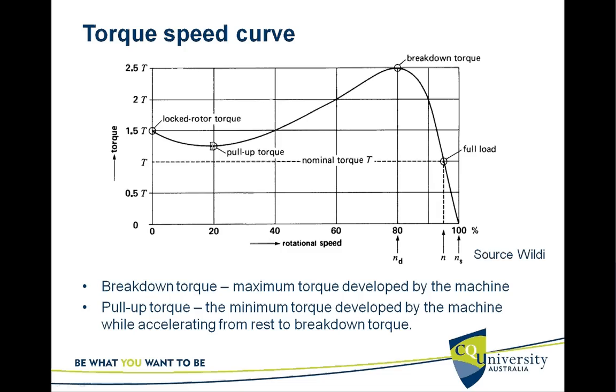Then the torque starts increasing, and at about 80% of the synchronous speed — not the nominal speed — the torque reaches a maximum called the breakdown torque, and then it starts dropping again.